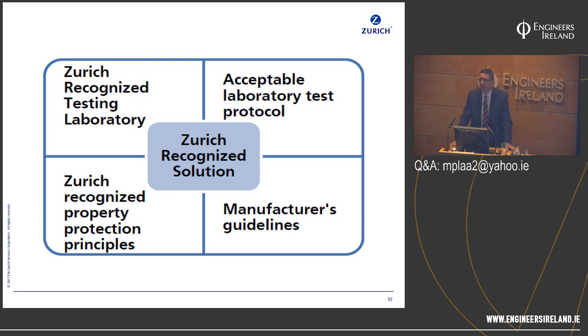So you cannot verify a system without that design manual, because if it says in the design manual the spacings are 2.5 metres by 2.5 metres, you cannot go on site without that information, because you need a tape measure and that information to verify and cross-map from the design manual to what the contractor's on site. And I can find systems on site where the spacings are at 2.5 by 2.5 and the installers put them at 4 by 4, totally invalidating the fire test and the design manual.